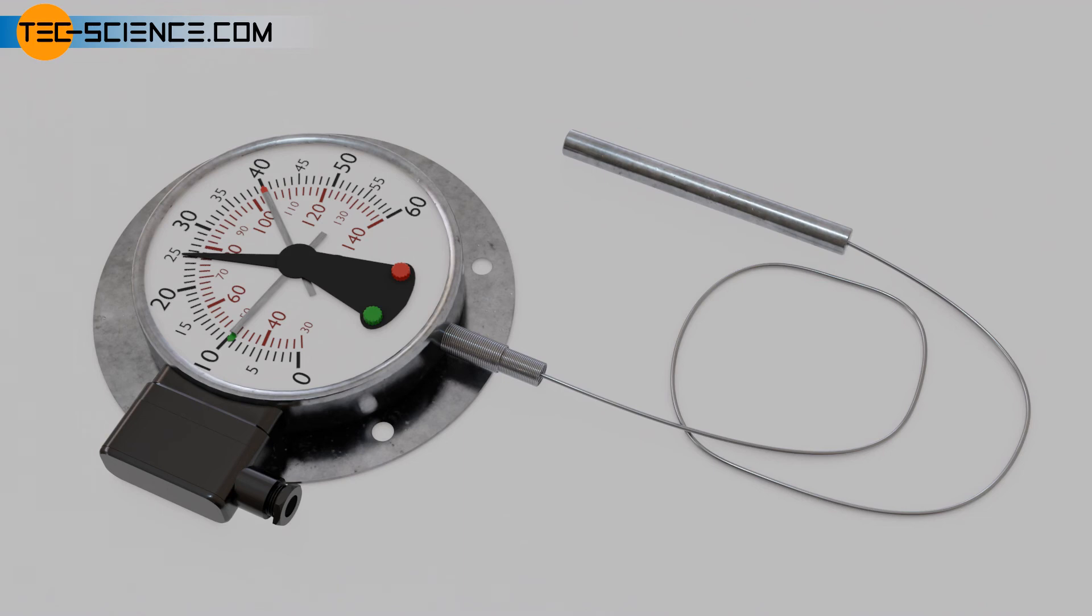However, it must be noted that liquid-in-metal thermometers react relatively slowly to temperature changes. This is due to the relatively large heat capacity of the thermometric liquid, as liquids generally require a relatively long time to adapt to the temperature changes.